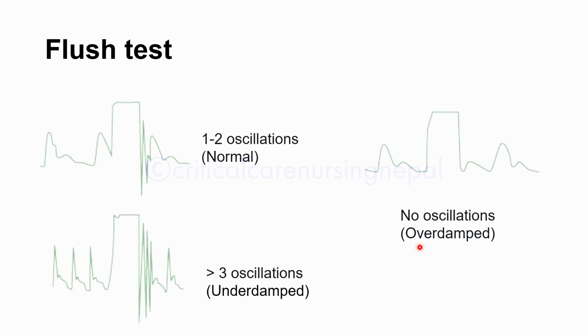Another thing, being a critical care nurse, we need to depend not only on the waveform or the number; we need to really identify whether the waveform shown is accurate and normal or not. For that we do a fast flush test, also called the square wave test. If we pull that flush device, a square is formed on the monitor. We can see the formation of this square, then we release the flush device and you see the oscillations. If there are 1 to 2 oscillations, that means your waveform is normal and you can trust the number you are getting on the screen. You need not worry about your numbers. You can trust your waveform.